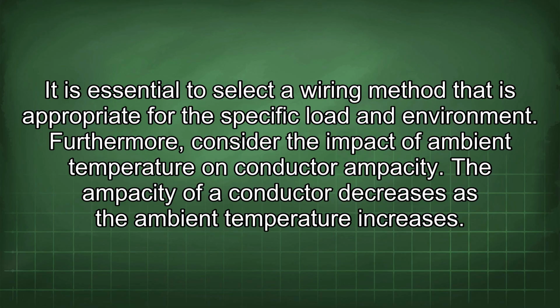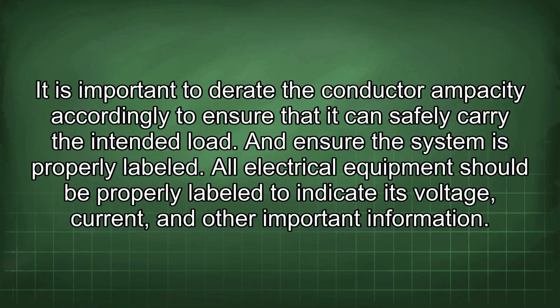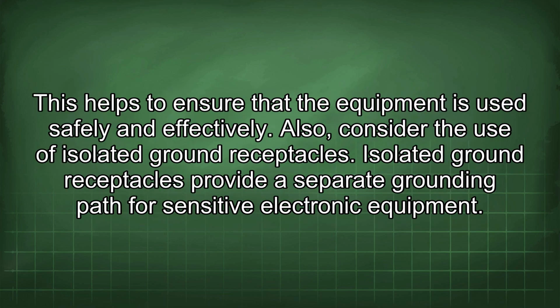Furthermore, consider the impact of ambient temperature on conductor ampacity. The ampacity of a conductor decreases as the ambient temperature increases. It is important to derate the conductor ampacity accordingly to ensure that it can safely carry the intended load, and ensure the system is properly labeled. All electrical equipment should be properly labeled to indicate its voltage, current, and other important information. This helps to ensure that the equipment is used safely and effectively.